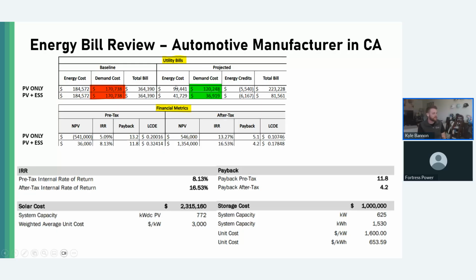Their demand cost baseline before adding anything, this shows PV only versus battery and ESS. Before, they're paying $170,000 a year in just demand costs. With PV only, you save 50 grand a year, which is pretty good. But adding PV and battery, you're saving nearly $140,000 a year, with payback periods of 4.2 years after tax. This is a no-brainer for this customer.